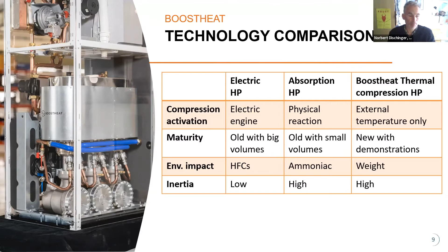The product concept is quite easy. It's the combination of the thermally driven gas heat pump with a conventional gas condensing boiler, both together supplied as a unit, with the intention to ease the sales process. This has shown that it works. We just come up with the promise, we are replacing your conventional oil or gas boiler within 1 to 2 days of standard work for a normally qualified installer. It connects to the existing heating distribution system. It connects to the hot water system. It can be operated with a domestic hot water external tank. We don't recommend it. We prefer not to store additional thermal energy, as we think gas is a better energy storage. Burn it whenever you need it, but not upfront.